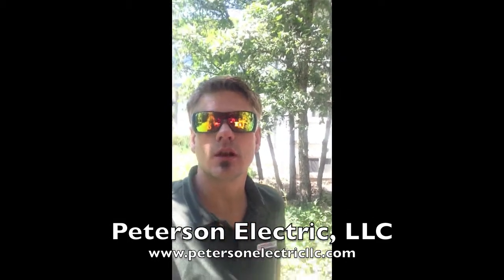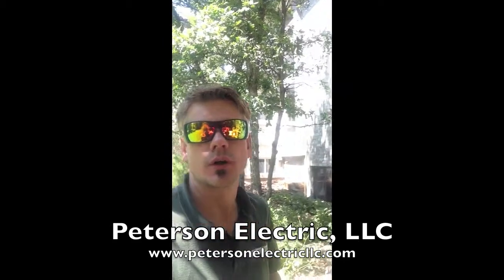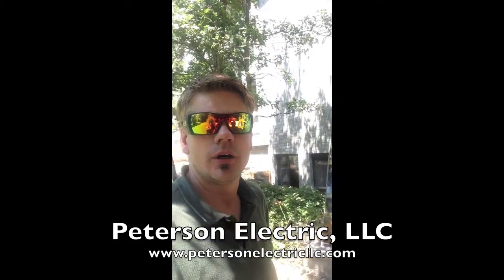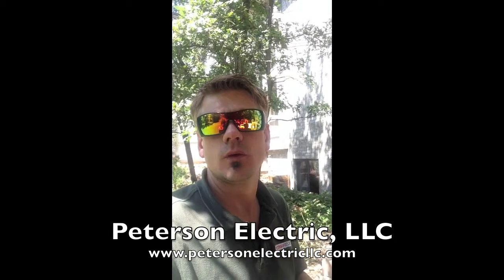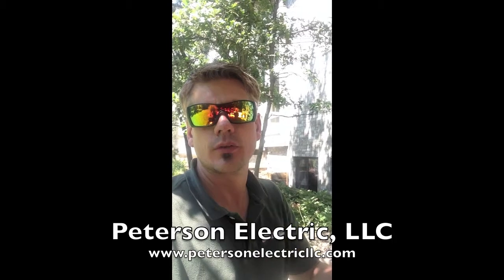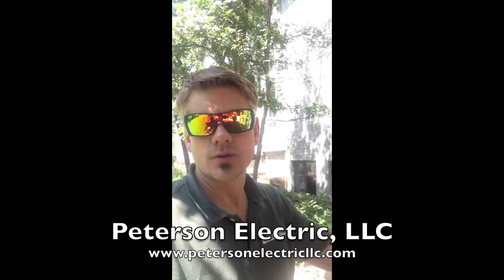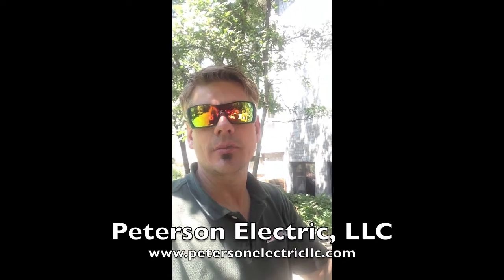We're in Littleton, Colorado, working outside here in a beautiful yard for one of our customers. Basically, we're installing a bunch of low voltage lights right now for them, and they're having some issues. The bulbs are good and the photo eye is good, and so is the transformer, but the connections are bad.